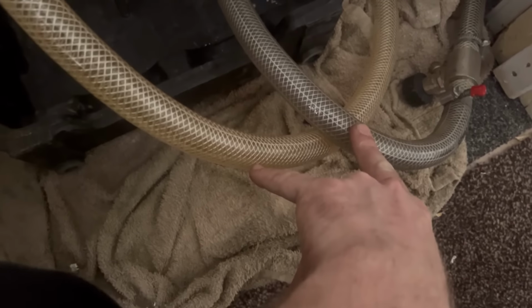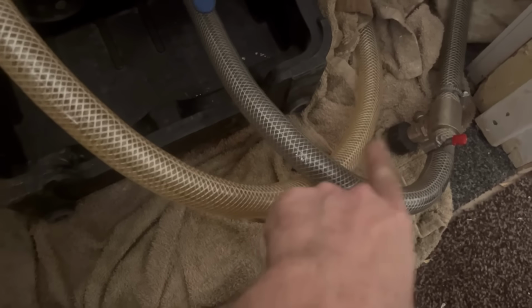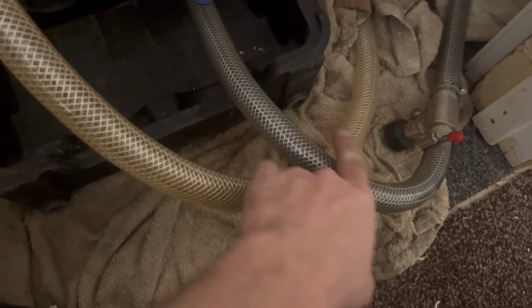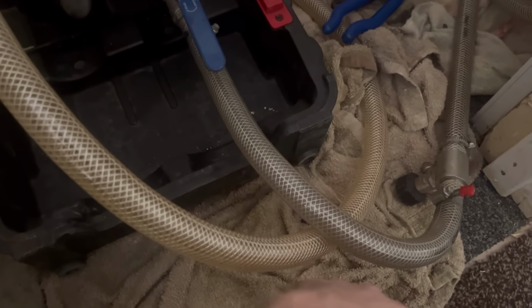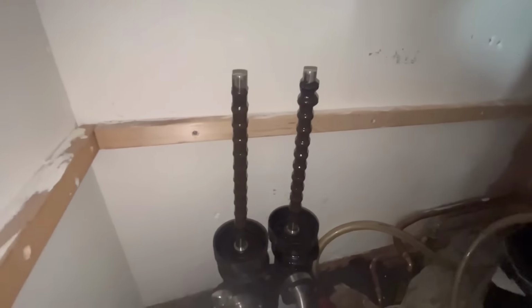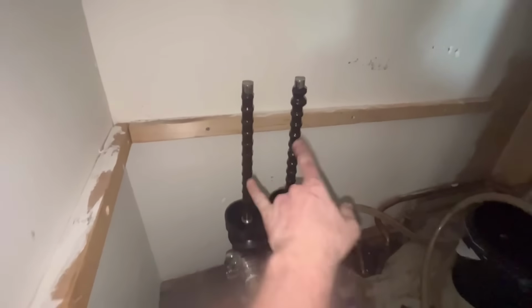The difference in the pipe, hopefully. There you go. The difference. So yeah, the agitation does wonders for getting the muck out of the system. So as I said, we'll do that for every single radiator. Yeah, it should give the system a good clean. There you go. Not a lot of muck we got out now. I haven't seen it that bad, but that's decent, to be fair.